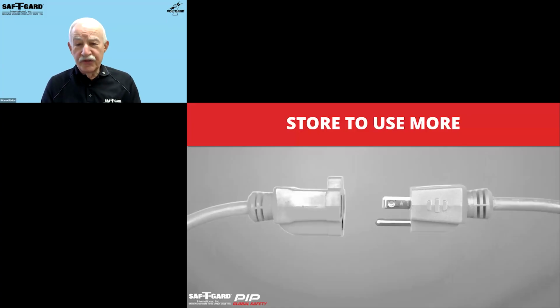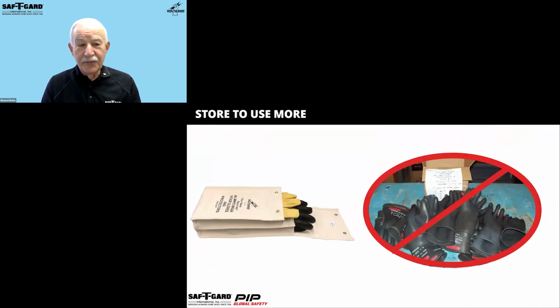Proper storage extends the service life of rubber insulating gloves. When not in use, store them in a suitable container, such as a canvas bag specifically designed for this purpose. There are canvas bags on the market now that have separate pockets for the rubber gloves and the leather gloves, which is that reminder every day to remove the protectors from the rubber gloves, store them properly, let them dry out from perspiration or use in inclement weather or other hazards, because at the bottom of that bag is actually a grommet that lets air circulate and let them dry.